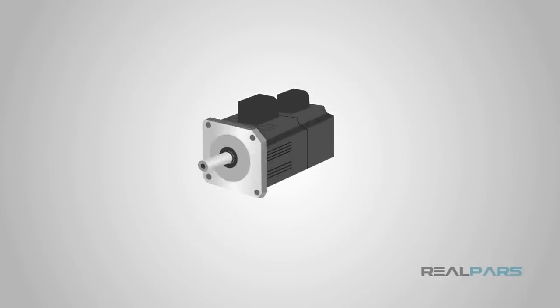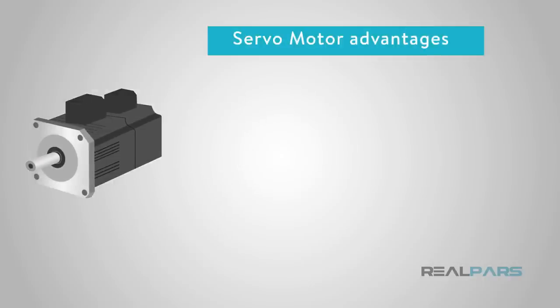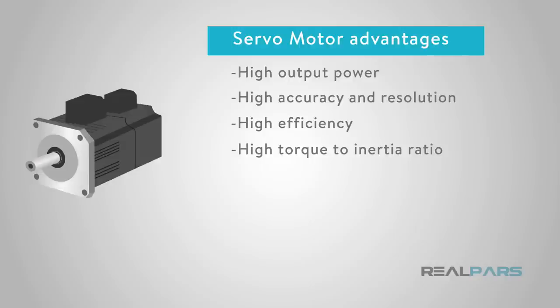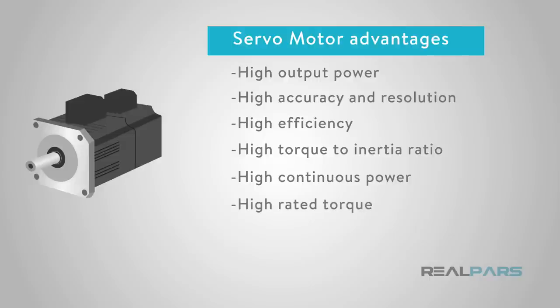Now, let's summarize the top servo motor advantages and disadvantages. Top servo motor advantages are: high output power relative to motor size and weight; encoder determines accuracy and resolution; high efficiency — it can approach 90% at light loads; high torque to inertia ratio — servo motors can rapidly accelerate loads; has 2 to 3 times more continuous power for short periods; has 5 to 10 times more rated torque for short periods; servo motors achieve high speed at high torque values; quiet at high speeds; and encoder utilization provides higher accuracy and resolution with closed-loop control.